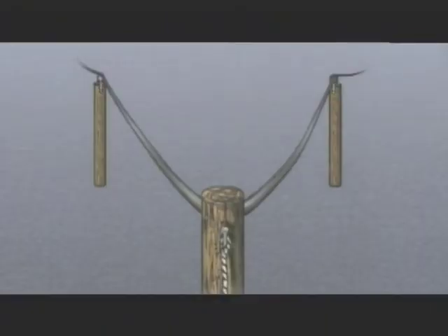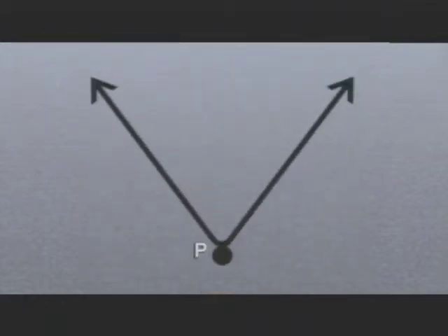Bisect tension can be defined as the pulling force of a conductor as it tends to pull a pole or structure into line with adjacent poles or structures. We can get a better idea of what's involved in determining bisect tension by using another illustration. This is an illustration of an angle or corner pole as seen from above.